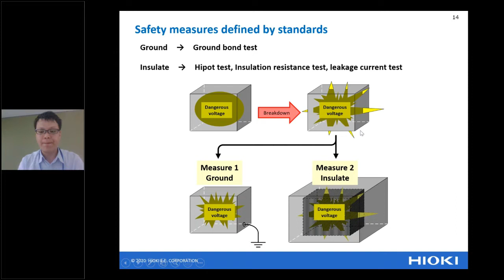The equipment class is determined by how the second protection is taken. There are two kinds of electrical instruments, class 1 and class 2. Class 1 is like this, as you can see. This equipment already has the countermeasure for insulation and ground. The first protection is insulation, and the second protection is ground. For class 2 equipment, in almost all cases insulation is the countermeasure to keep the equipment safe.